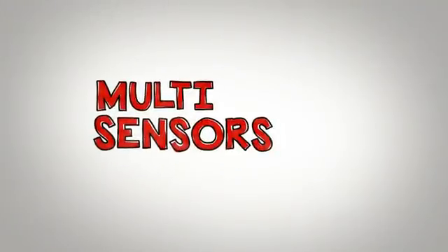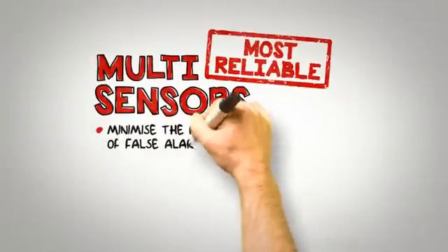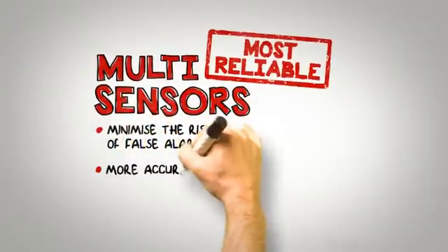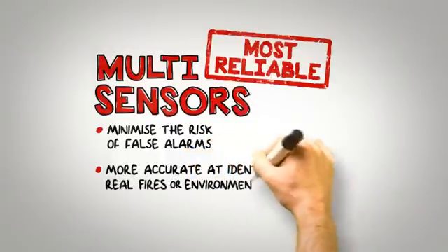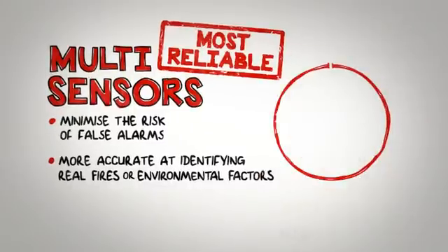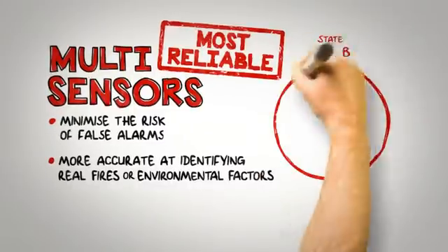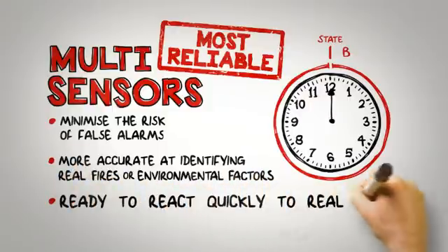Multi-sensors. The most reliable option for many environments is the multi-sensor. These devices can help to minimize the risk of false alarms as they are much more accurate at identifying whether there is a real fire or if the alarm is being triggered by an environmental factor such as dust or steam. Each multi-sensor can be set with different sensitivity states and be programmed to react differently depending on the time of day. These intelligent features help to remove any risk of false alarms but are ready to react quickly to real fires.